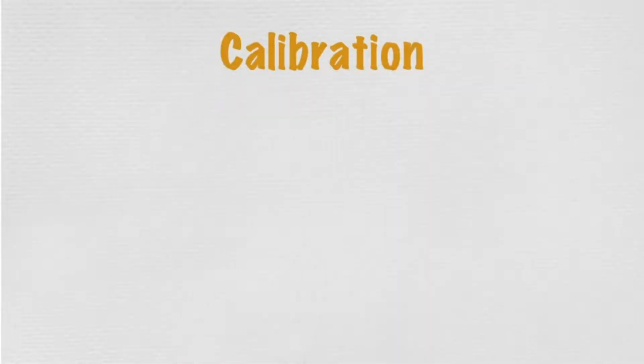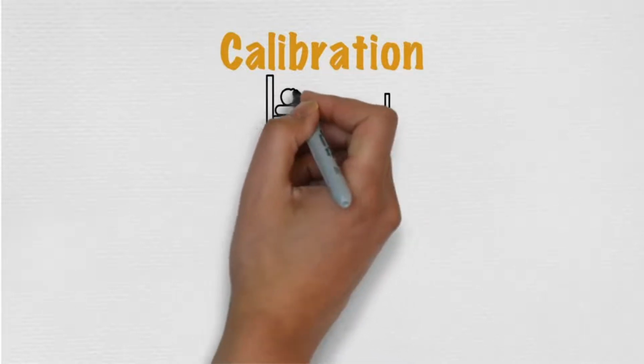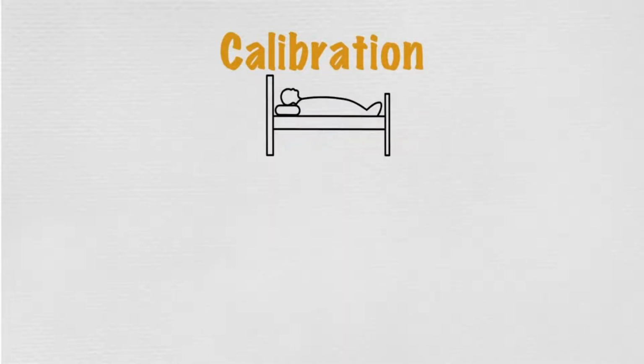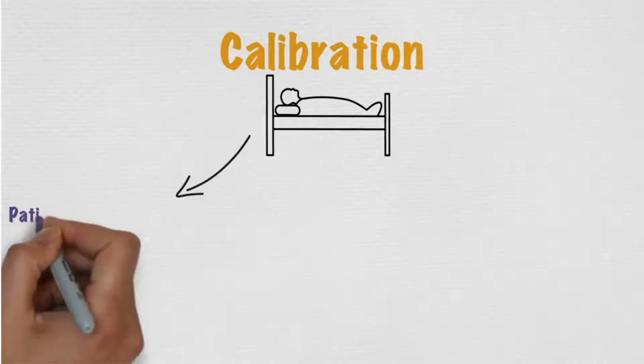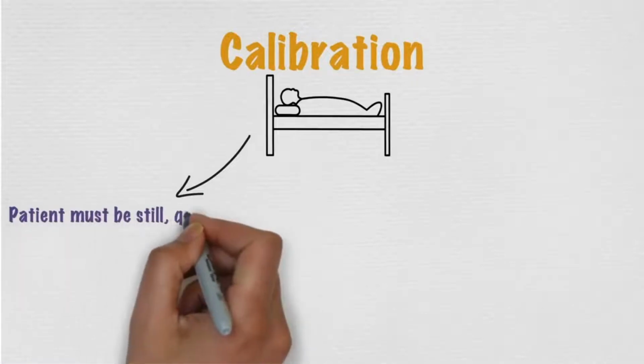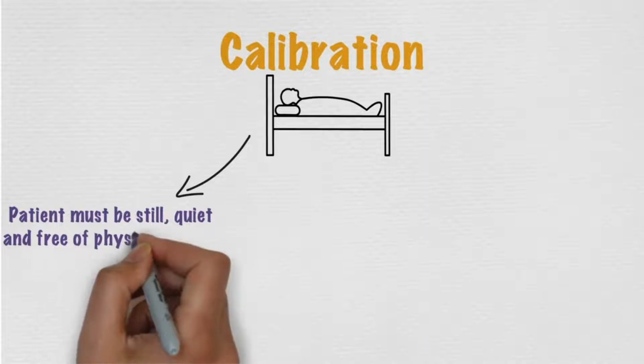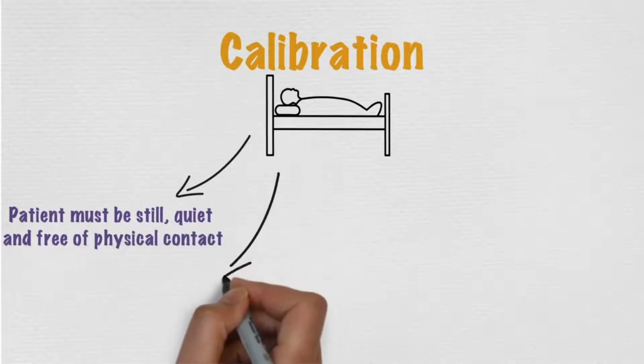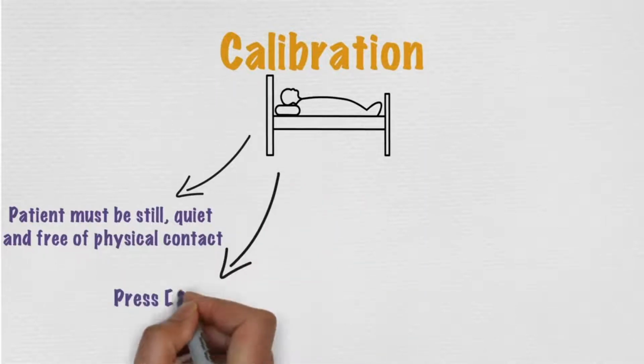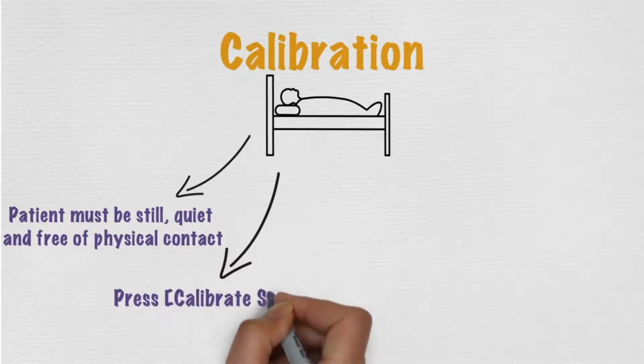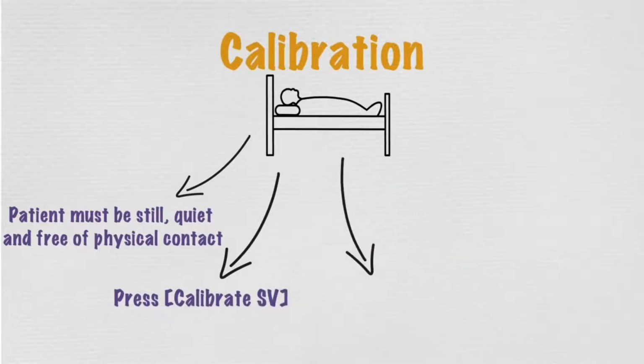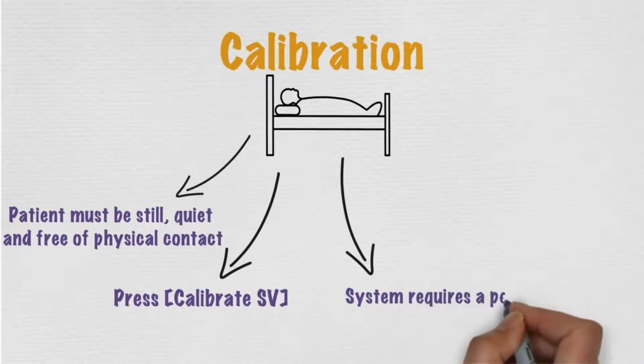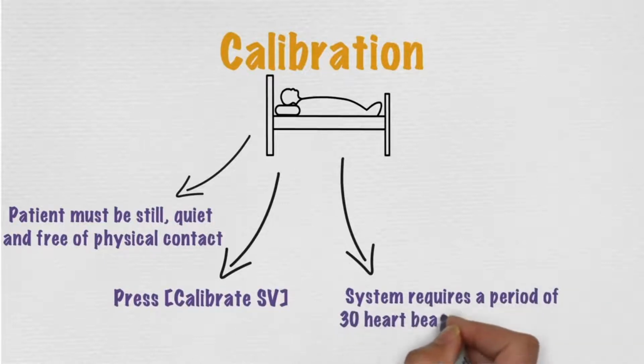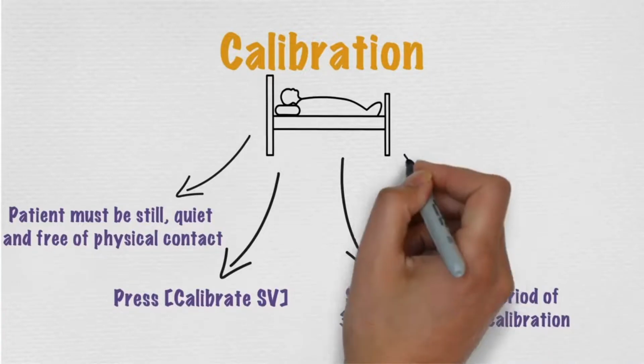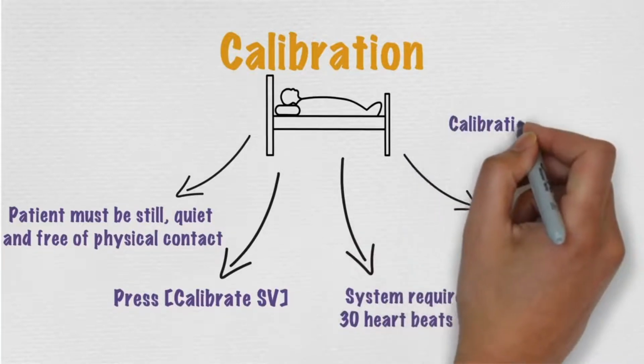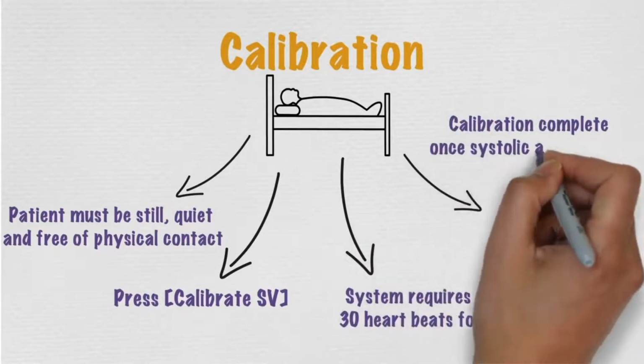Before obtaining any stroke volume measurements, calibration must be performed. For this, the patient must be still, quiet, and free of physical contact with others. Press the Calibrate Stroke Volume button. The system requires a period of 30 heartbeats for calibration, and a banner will flash during this period. Calibration is complete once systolic and diastolic pressures have been added.